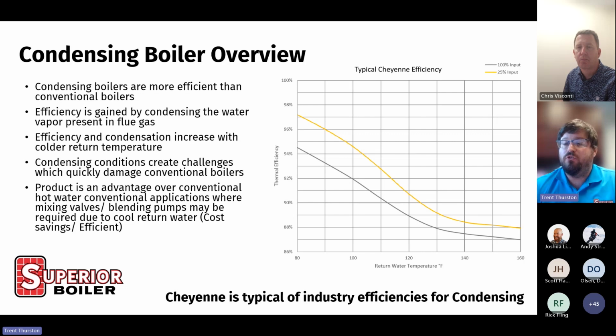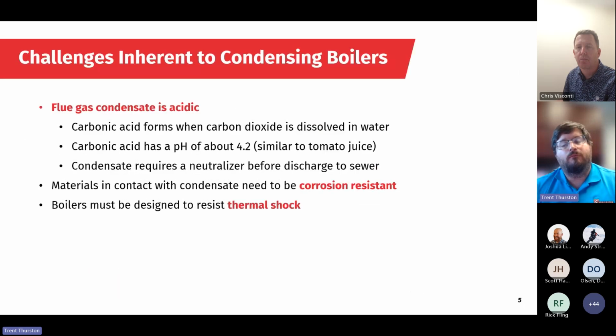Now, since we do want this cold water coming back to the boiler, that does create certain design challenges for us that we address with our Cheyenne. The first is that the flue gas is acidic, so that water vapor that we condense into liquid water now has carbon dioxide in the flue gas dissolve into it. This forms carbonic acid. It's a relatively weak acid, but it still will cause damage to anything that's not designed to resist corrosion. So the other issue that we have with the cold water is thermal shock and thermal stresses. These are caused by temperature differentials between the cold water and the hot gas. So we have potentially 100-degree water coming into the boiler, and the gas in the furnace will be over 2,000 degrees. So the differing rates of expansion cause thermal stresses.